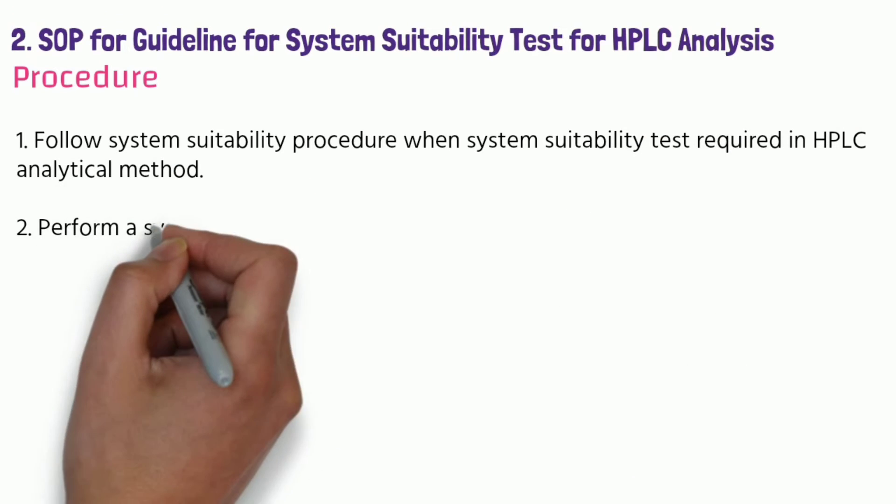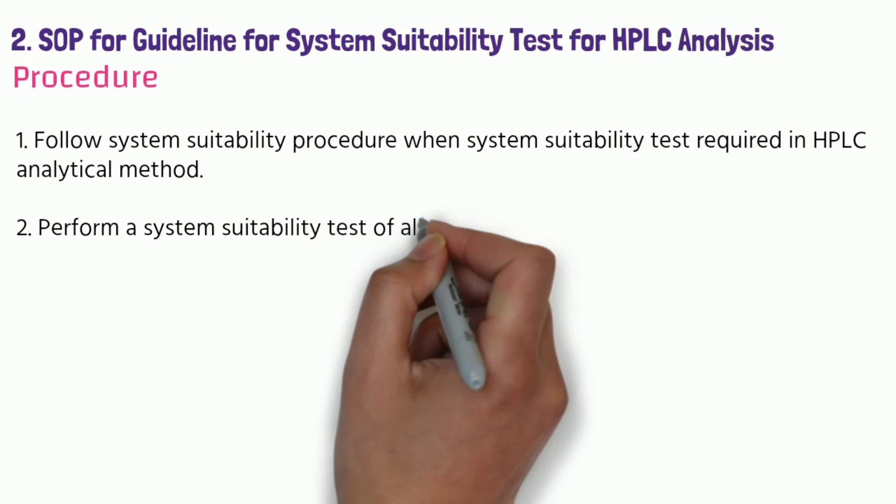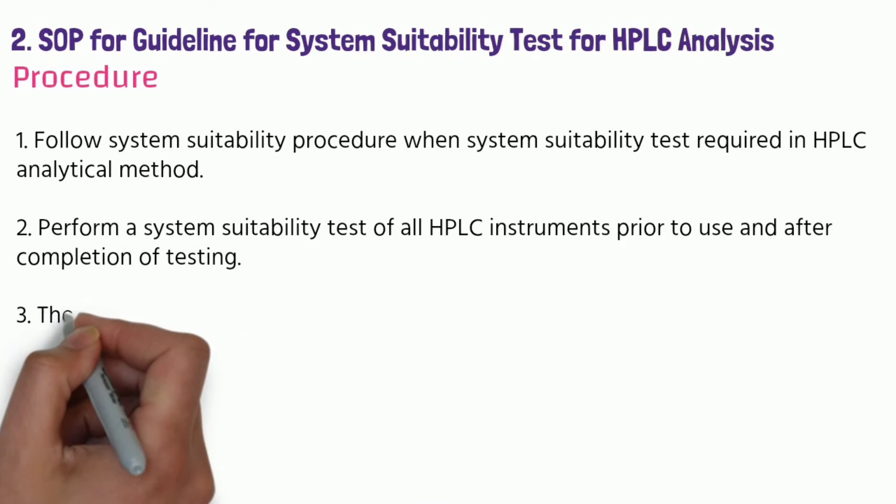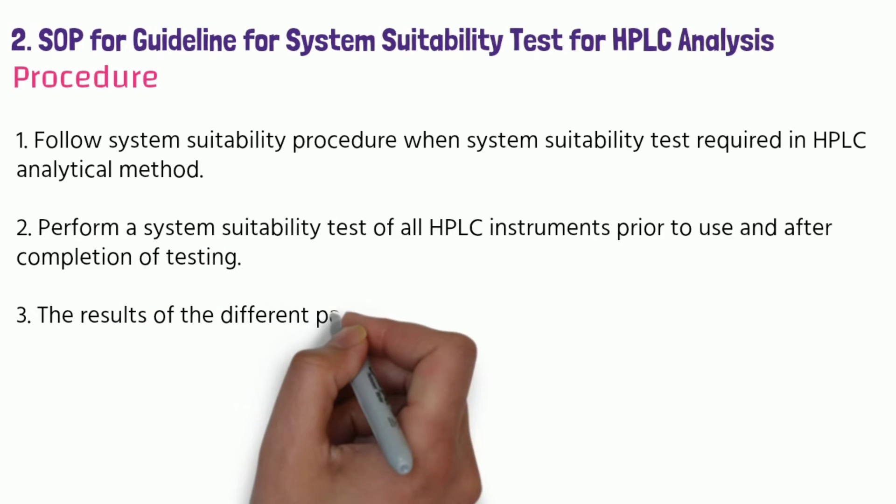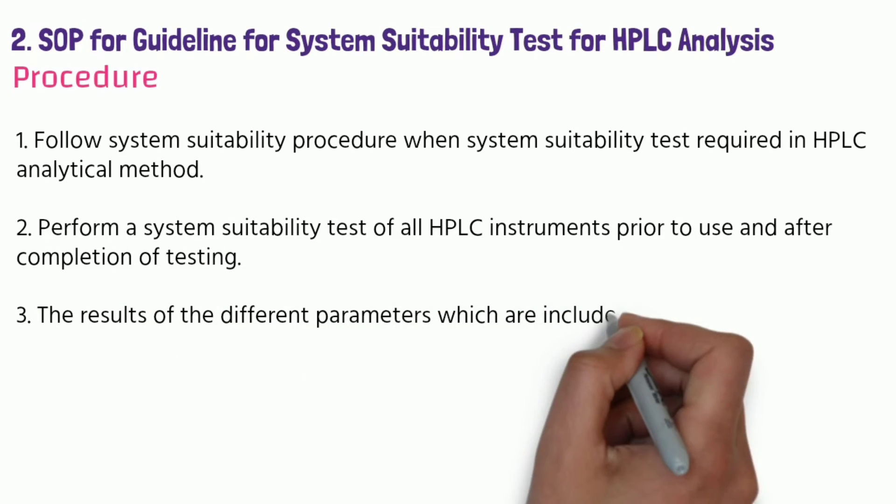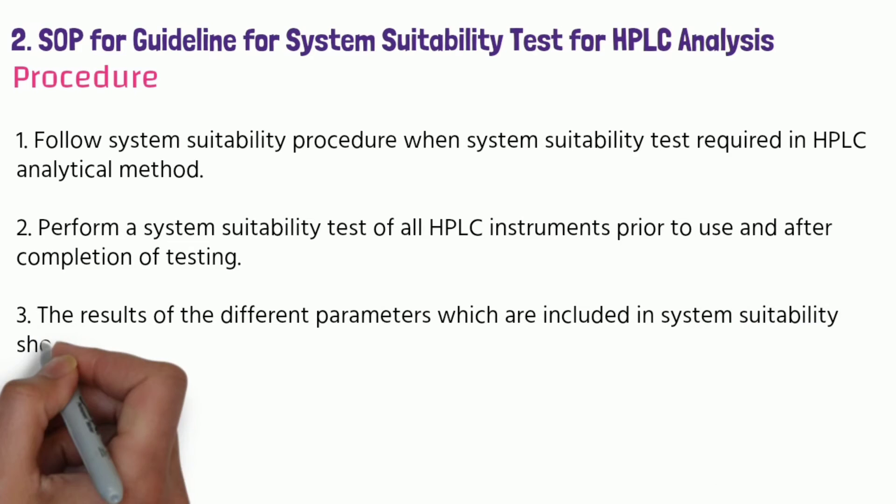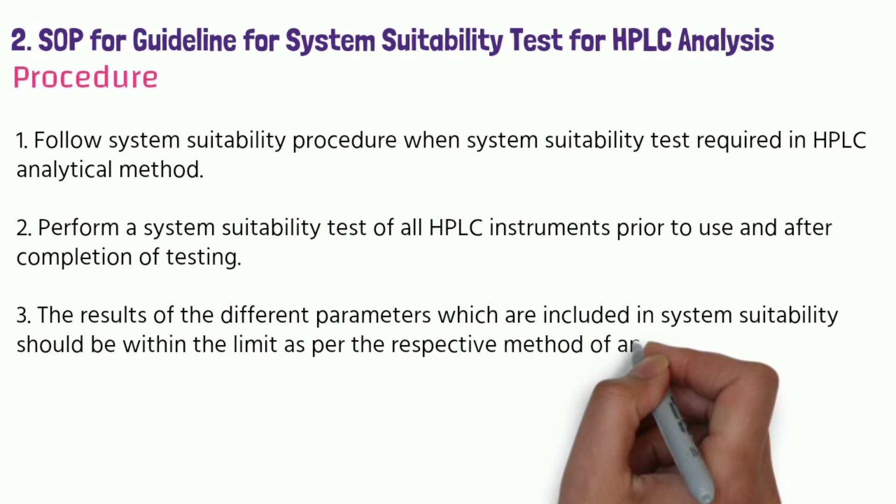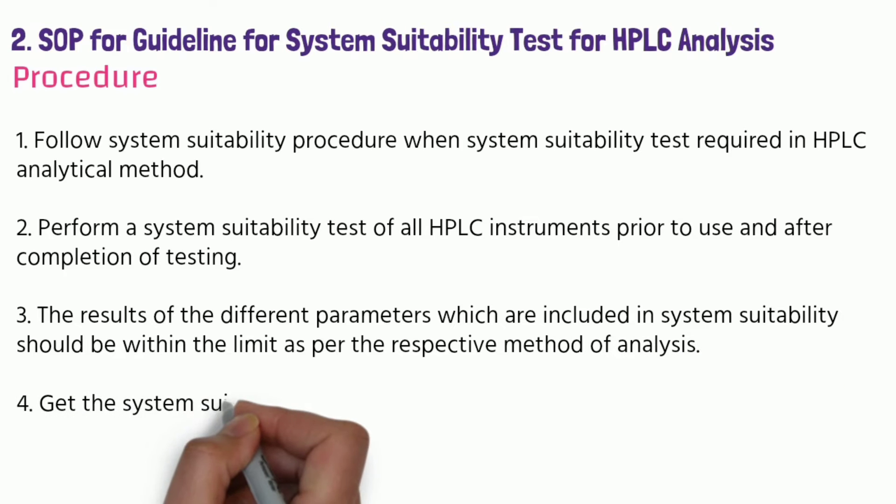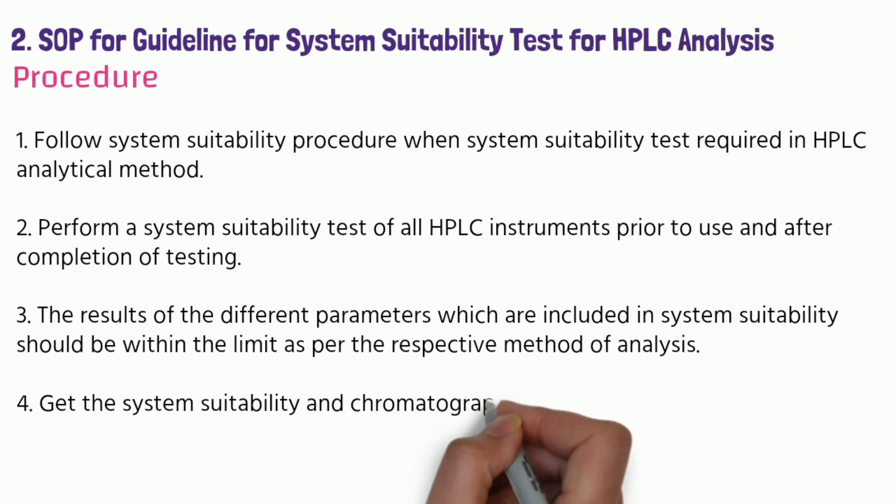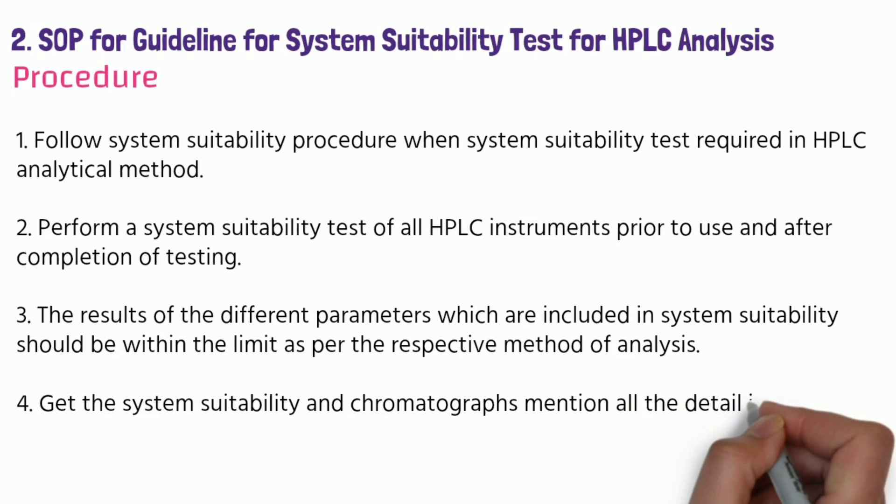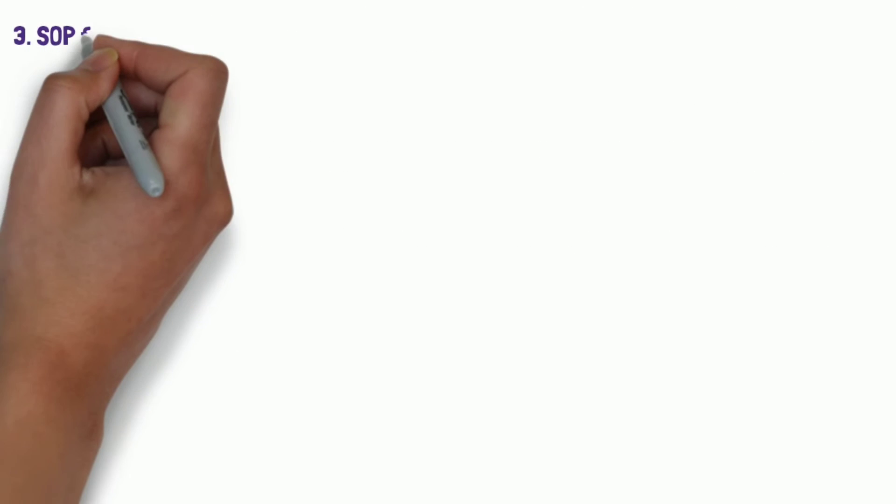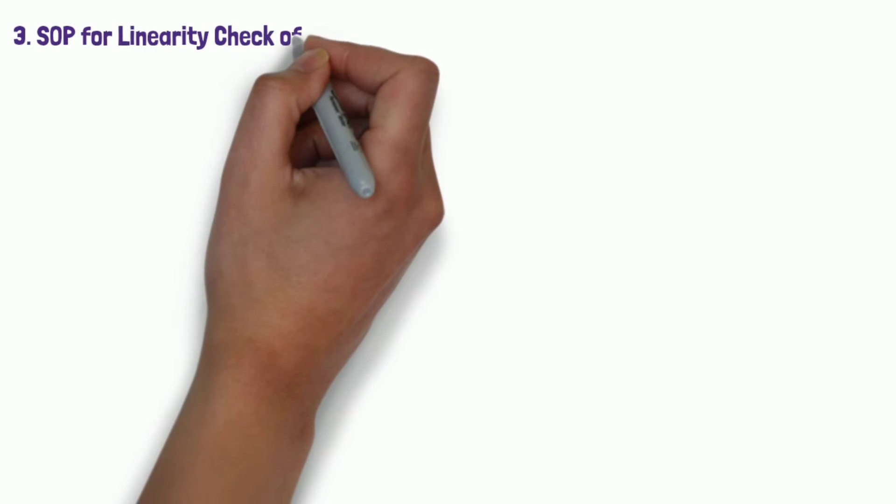Perform a system suitability test of all HPLC instruments prior to use and after completion of testing. The results of different parameters which are included in system suitability should be within limit as per respective method of analysis. Get the system suitability and chromatographs. Mention all the details in respect to product data sheet.